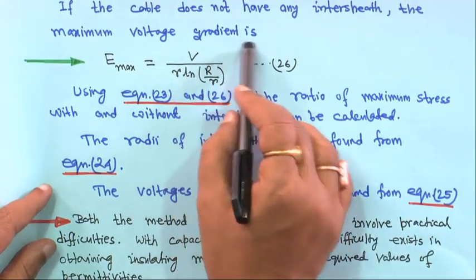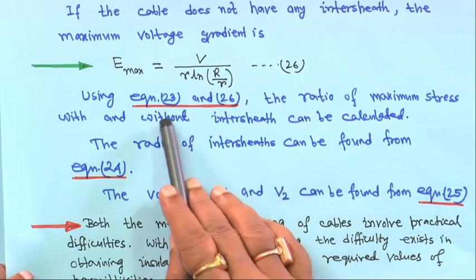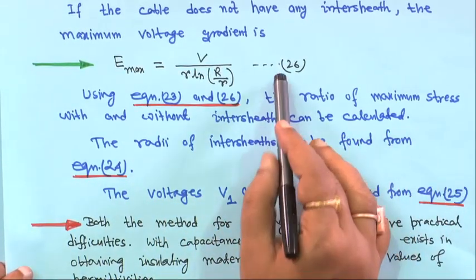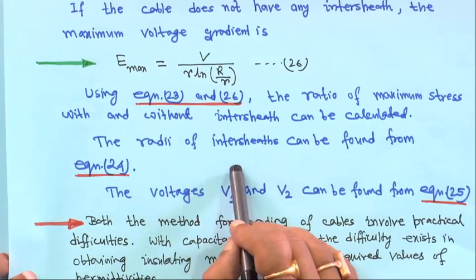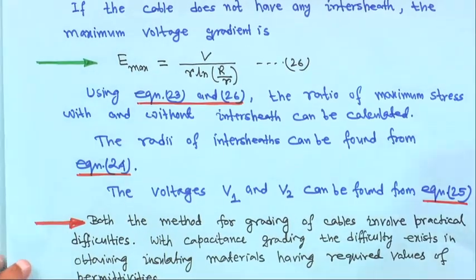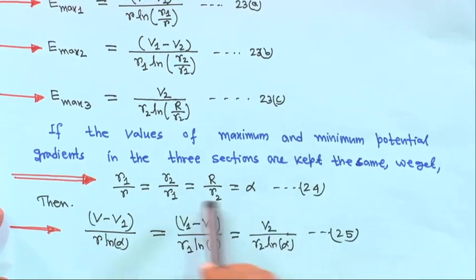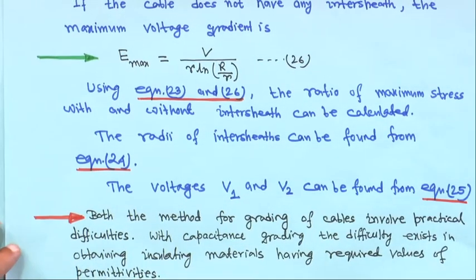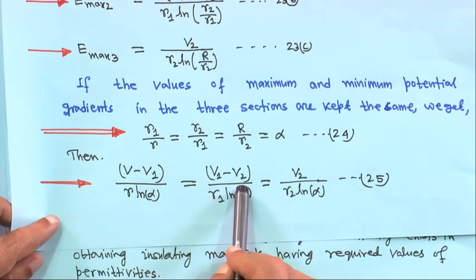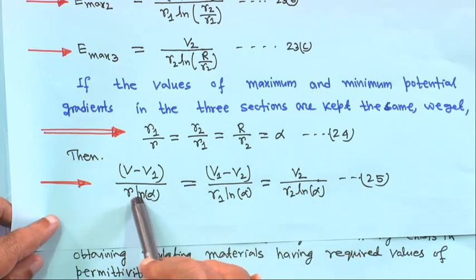If the cable does not have inter-sheets, the maximum voltage gradient is E_max = V / (r·ln(R/r)), which is equation 26. Using equations 23 and 26, the ratio of maximum stress with and without inter-sheets can be calculated. The radii of inter-sheets can be found from equation 24, and voltages V₁ and V₂ from equation 25.